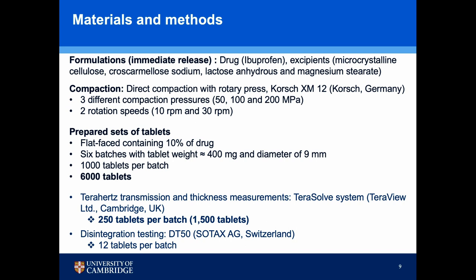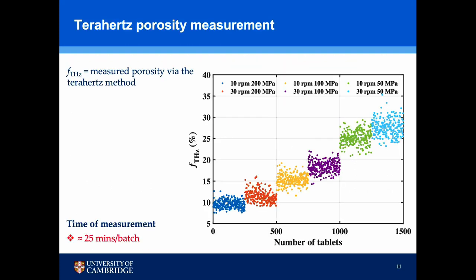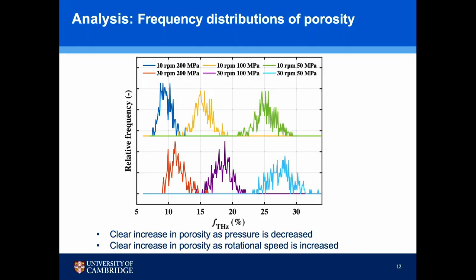Out of the 1,000 tablets per batch, we have currently been able to measure 250 tablets, giving us 1,500 tablets in total measured. These are the data I'm going to talk about. As you can see from the measured porosity across all 1,500 tablets, by visual observation we can clearly see that the porosity changes based on the compaction parameters. Here, we are using about 25 minutes to measure one batch of 250 tablets. This is a frequency distribution of the measured porosity, and you can also clearly see the differences and how uniformly they are distributed.